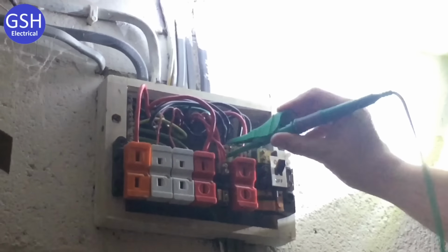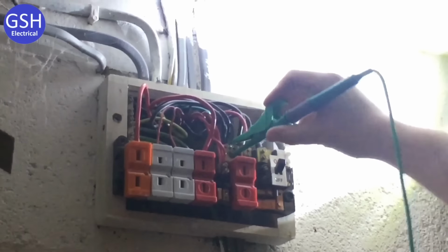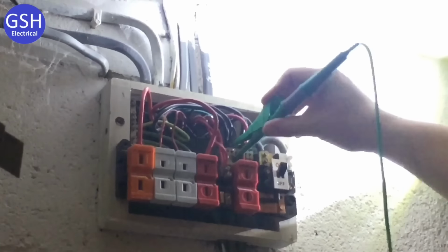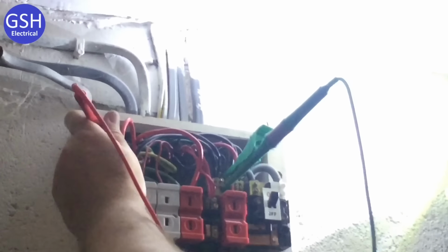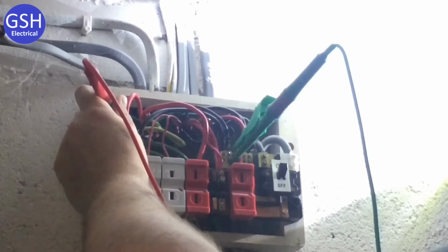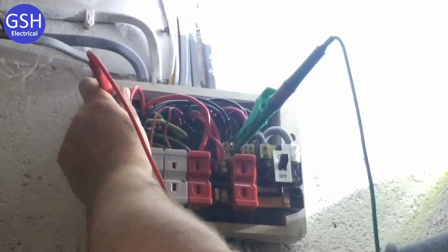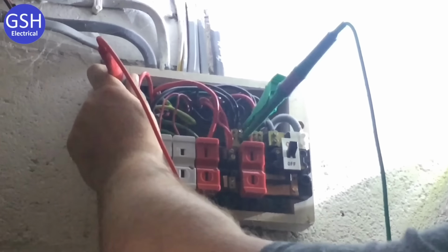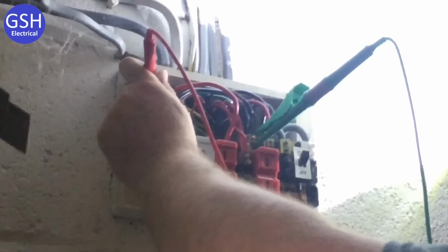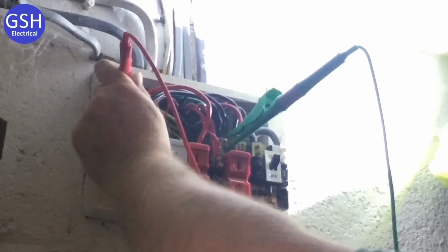Good. I've got 52 mega ohms. Okay, brilliant. Which conductors are we not going to test between? We're not going to test between line and neutral. Good. Why are we not testing between live conductors this time? Because we don't want to put 500 volts through anything that we're not sure is unplugged. Okay, and which area of the house are we worried about at the moment? About the kitchen. We've got a lot of appliances under there that we can't guarantee are turned off, is that correct?